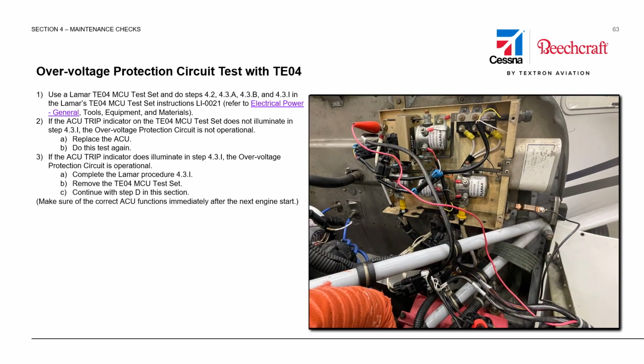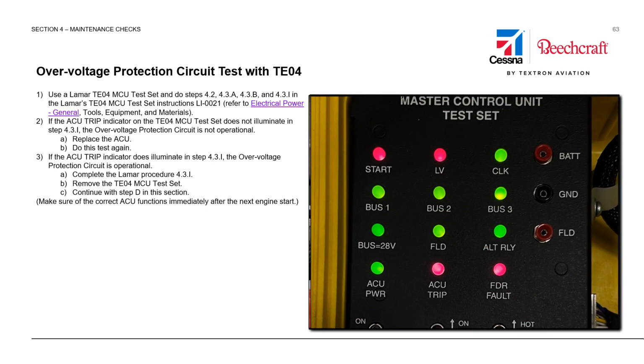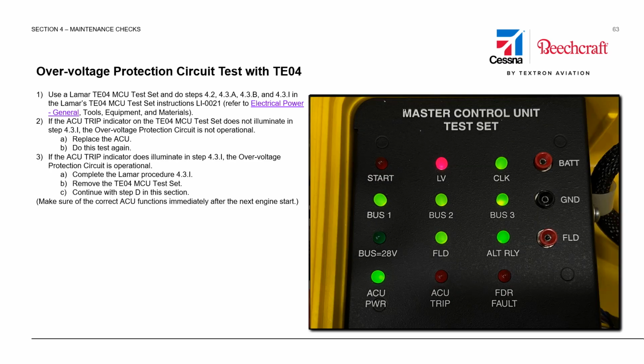With all of our connections made, we'll start the test following the LI-0021 manual that is included with the test set. We will start with a lamp test to verify all the indicators on the TE-04 are working properly. Next, we will verify that normal operation looks correct with power available from all of the fuses and/or breakers as applicable. We could ignore the red low voltage light, but we should see no other fault lamps.